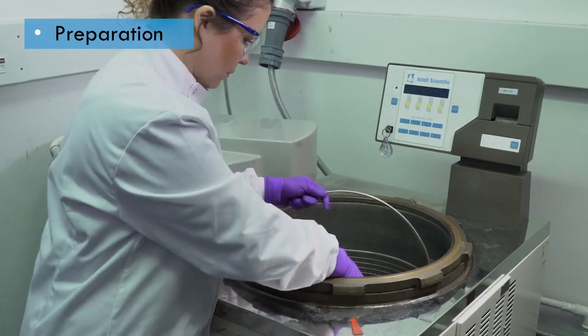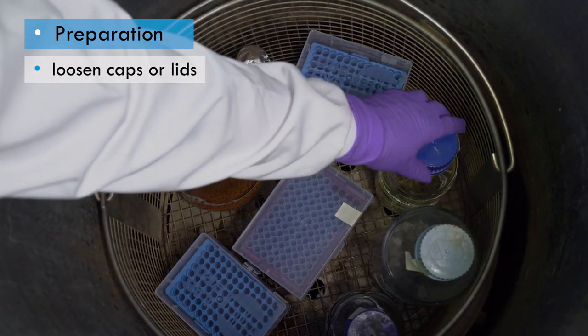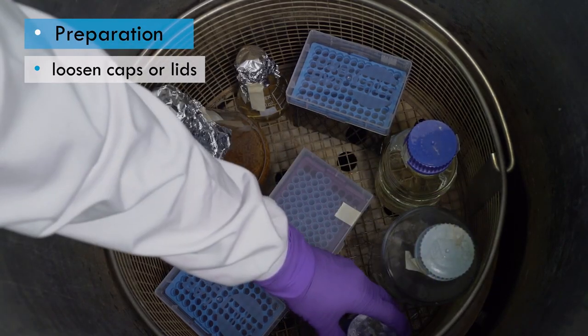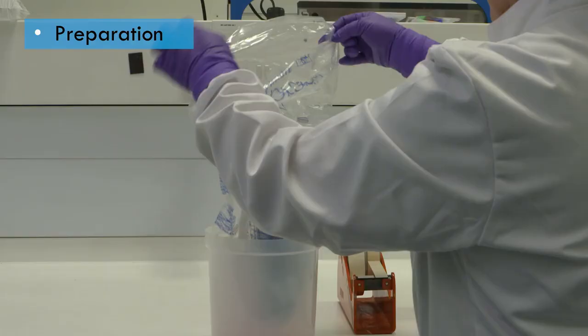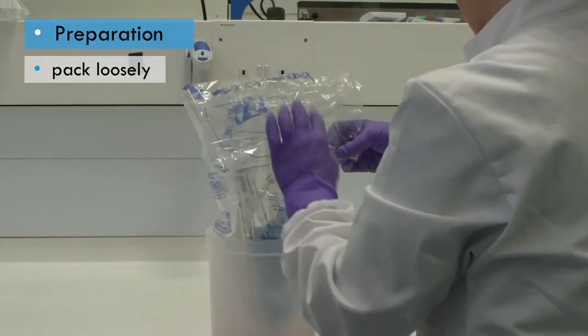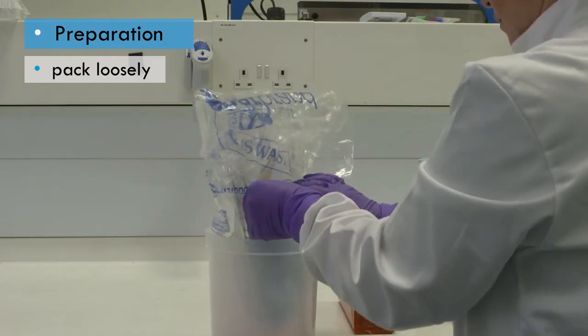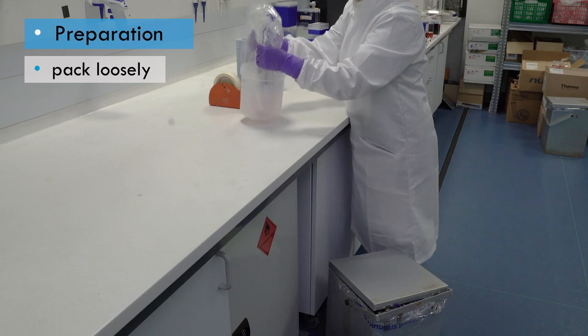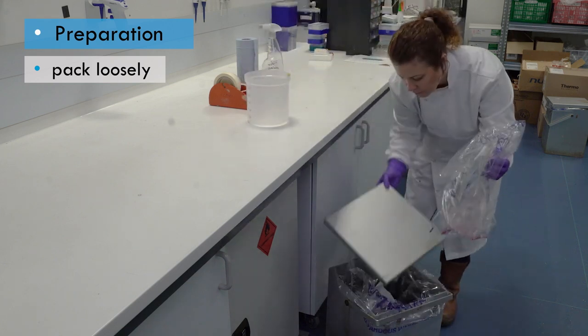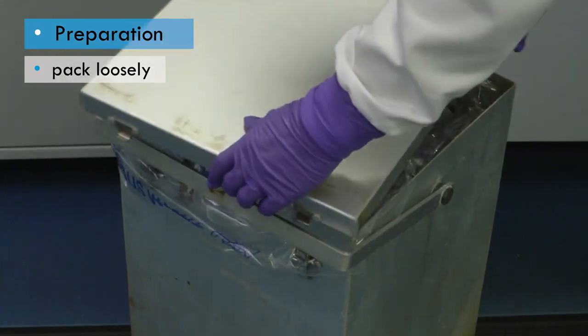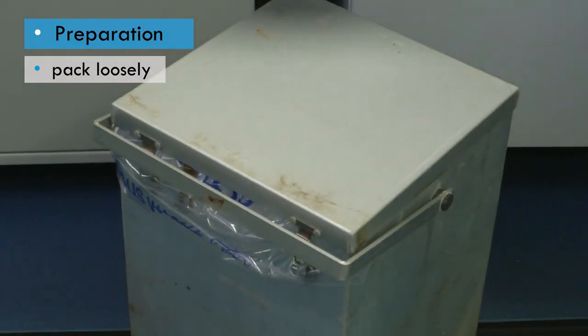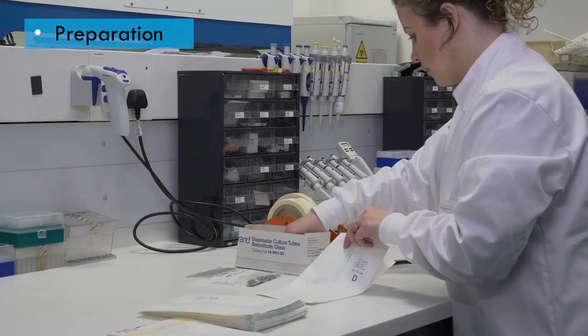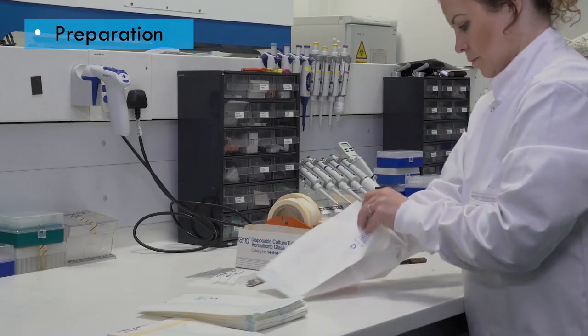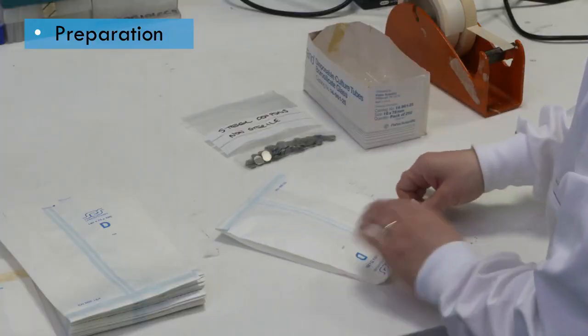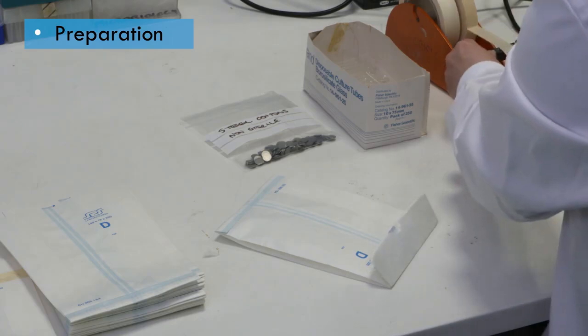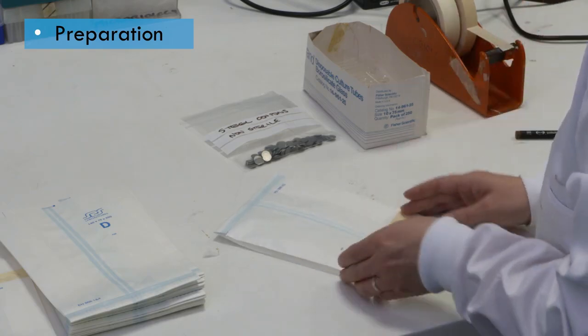It's important to note that when autoclaving bottles, either full or empty, it's advisable to loosen the caps to ensure that pressure differentials don't cause them to break. Waste to be autoclaved must be packaged such that steam can penetrate the entire load. Plastic autoclave bags must be loosely taped, ideally with indicator tape, and not tightly bound. These should then be placed in autoclavable boxes to contain their contents, as the plastic bags may melt and leak. Some packaging, such as paper autoclave bags, often used for sterilizing small items like steel coupons and spatulas, is designed so that the steam will permeate through the packaging, which remains completely sealed.